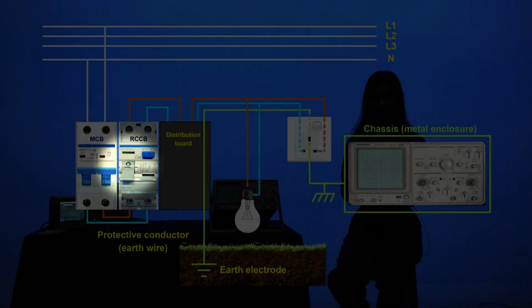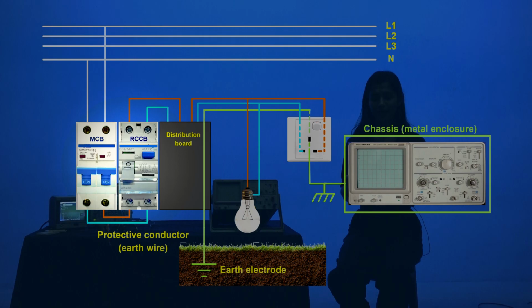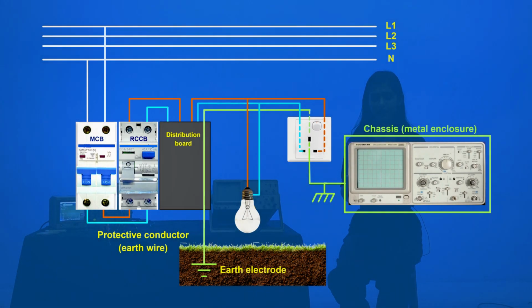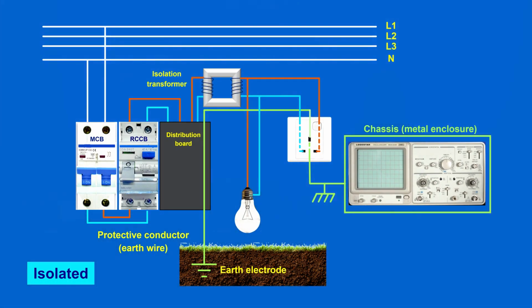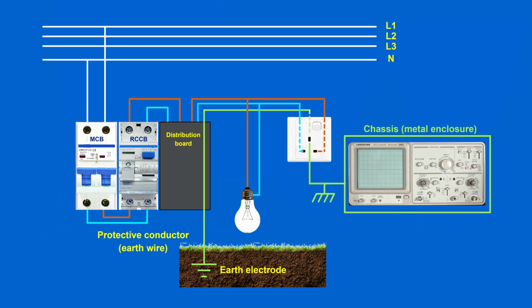Before connecting any power line to oscilloscope inputs, we must ensure that the power supply to the oscilloscope is isolated from the main supply. Otherwise, the protective conductor should be disconnected from the socket.